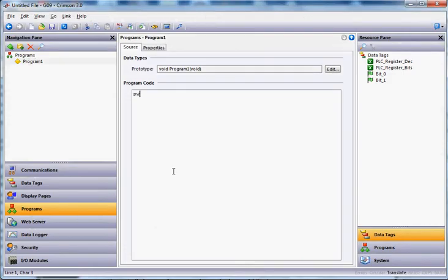We'll go here and we'll just type switch, open parentheses. I'm going to monitor this tag, the decimal equivalent, so I'll drag this guy out here like this, end parentheses, enter. And then if you remember from my classes, I like to teach where you do open brackets, and then I'll do enter, give some space, tab across, and close brackets. Now between here, I'm going to say case 1, whenever the PLC equals number 1, I might do this. I'll type GotoPage, open parentheses, page 1, end parentheses, semicolon, enter, and then if that condition's true, I'll do a break. Means I'm done with the test here.